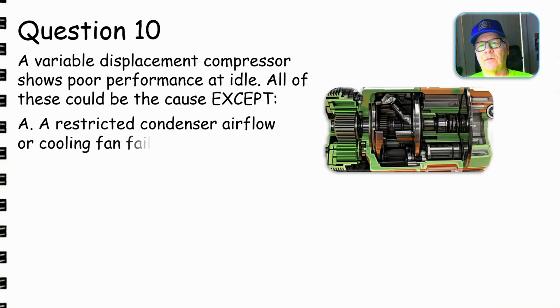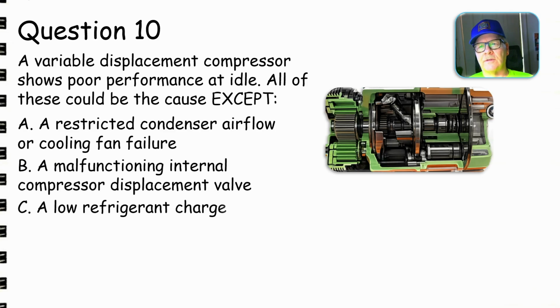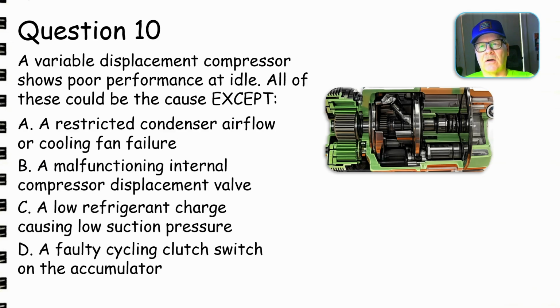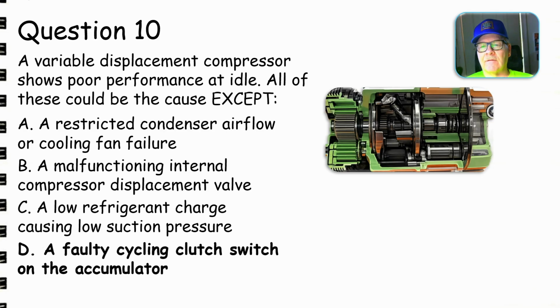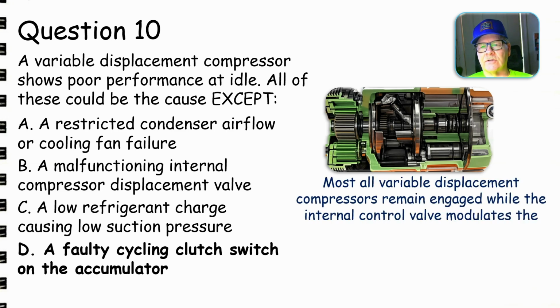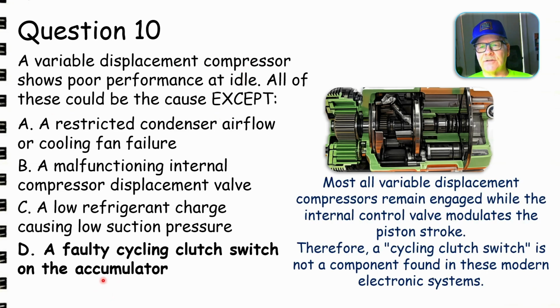Question 10: a variable displacement compressor shows poor performance at idle. All of these could be the cause except—one, you could have restricted condenser flow, is that true? Or cooling fan failure, maybe a malfunctioning internal compressor displacement valve, or a low refrigerant charge causing low suction pressure, or a faulty cycling switch on the accumulator. This is not going to be a good answer here. It's the except answer because most all variable displacement compressors do not have a clutch cycling switch.